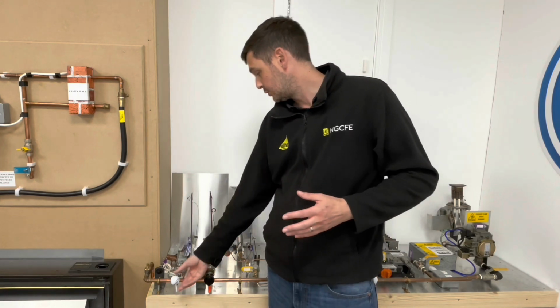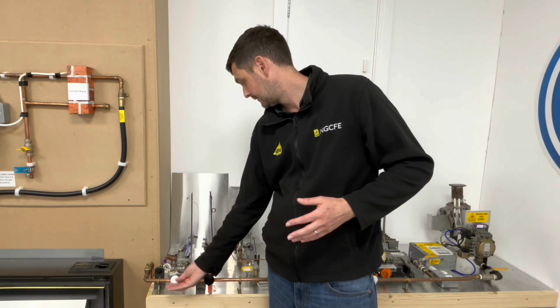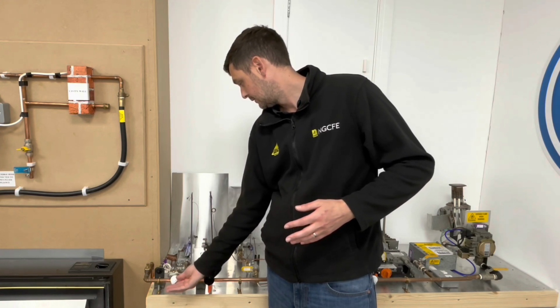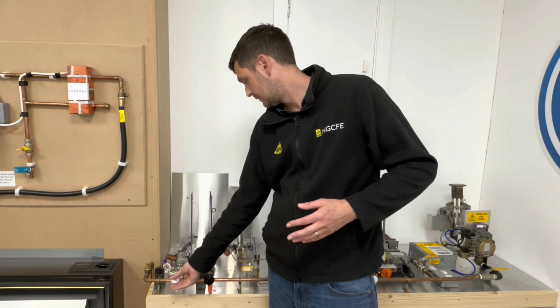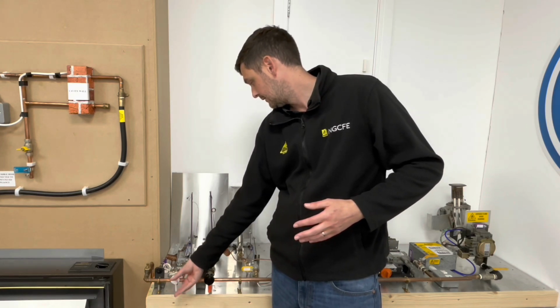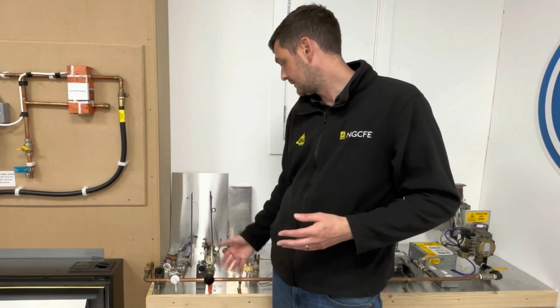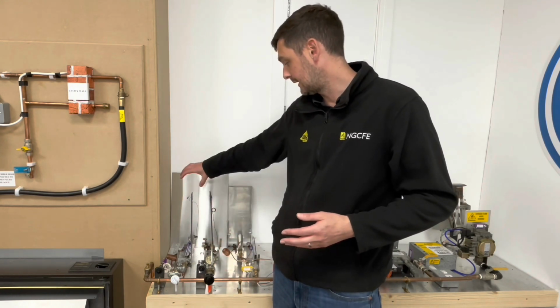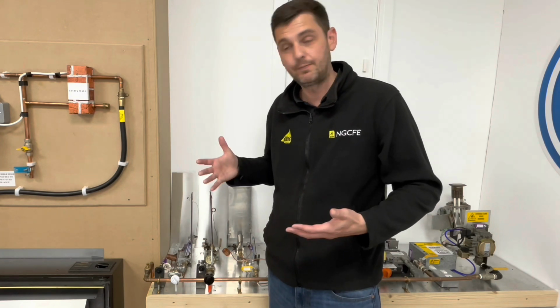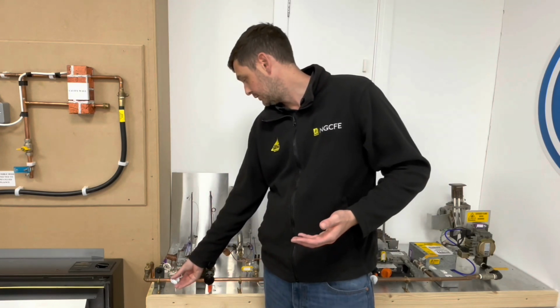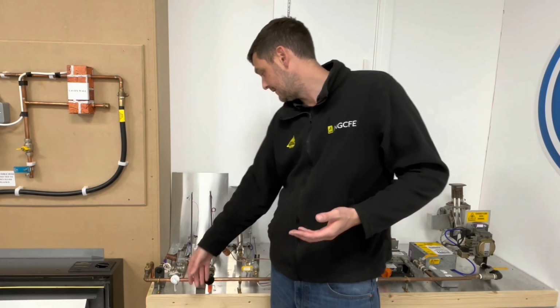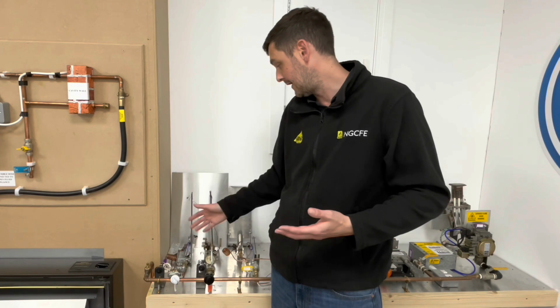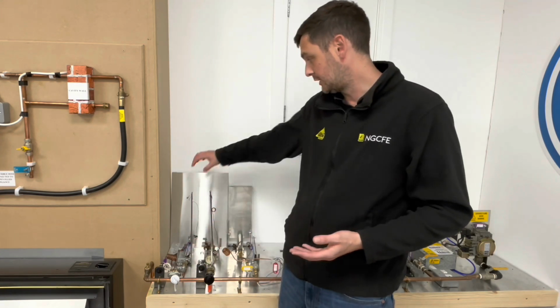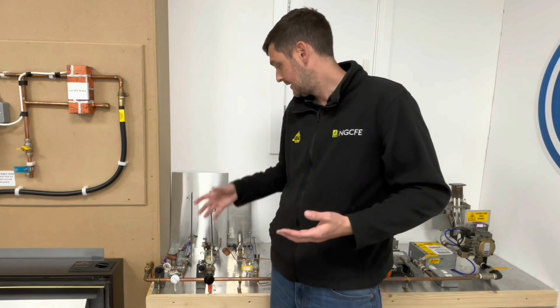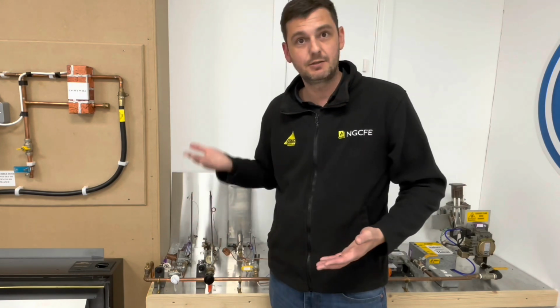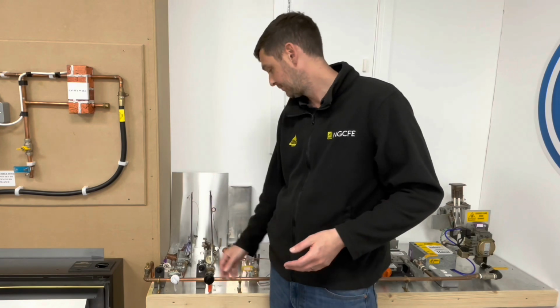So once that then goes down to low flame by just a setting, you'll see it's now just gone down to its lowest setting. And now, because it's starting to get cool again, it's just starting to rise back up. At which point, if I turn the thermostat down even further, you'll see there's only a small amount of gas being allowed through via the bypass. And then eventually, once this cools down, the vapour contracts, and then the bellows open again, allowing the gas pressure to increase to the main burner.